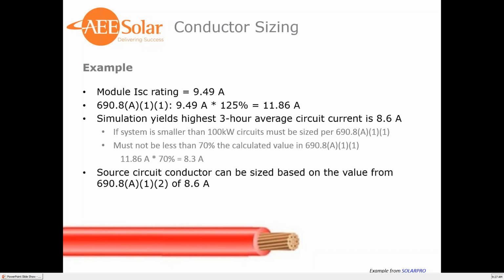So this is saying that our source circuit conductor can be sized based on the value by the simulation software of 8.6 amps. So you could essentially see in larger systems reduced wire sizing for your PV source circuits, which could drastically reduce cost. There could definitely be a lot of benefits from it.